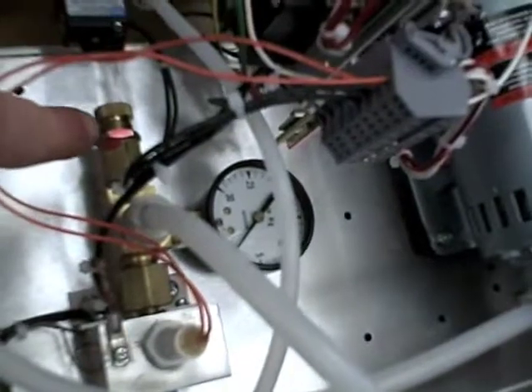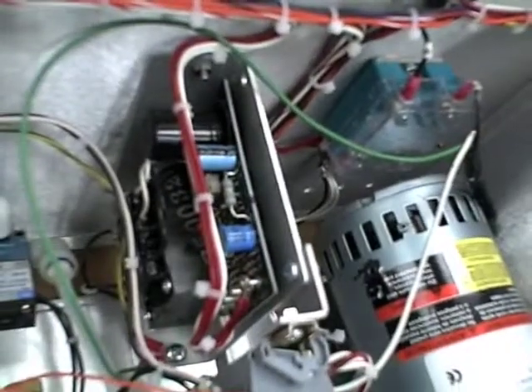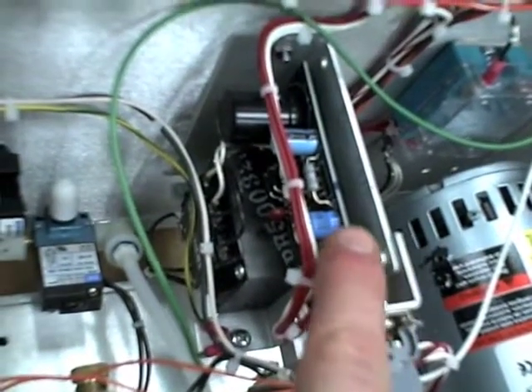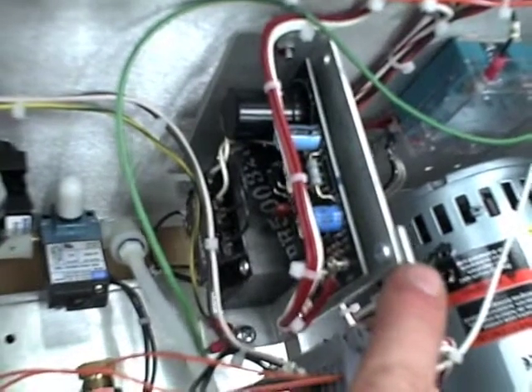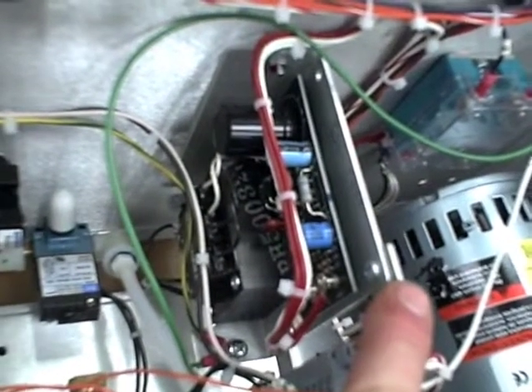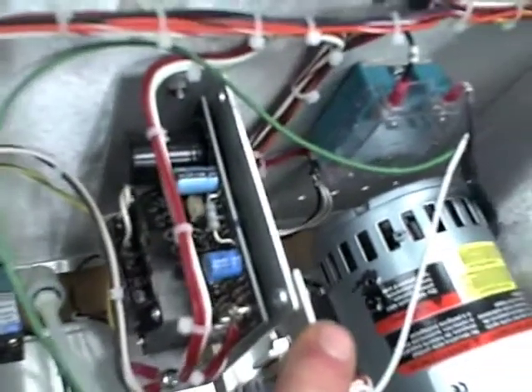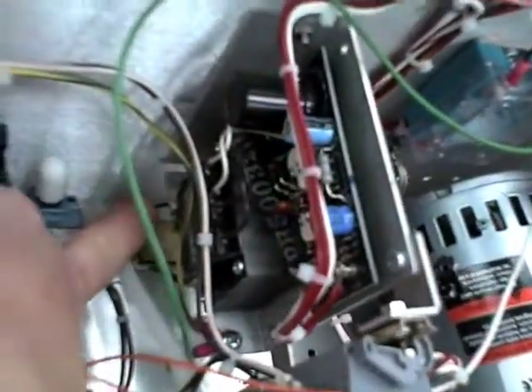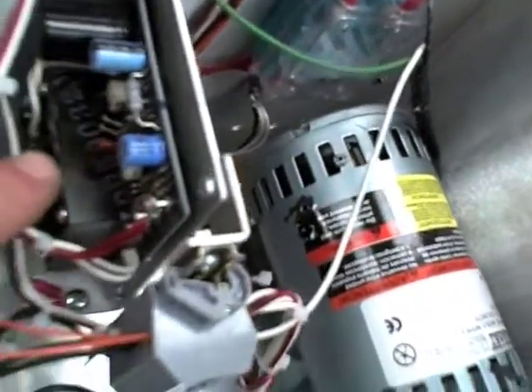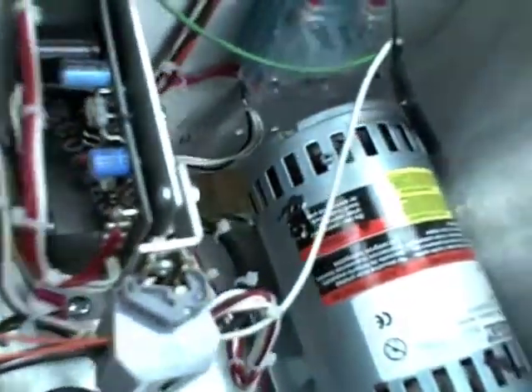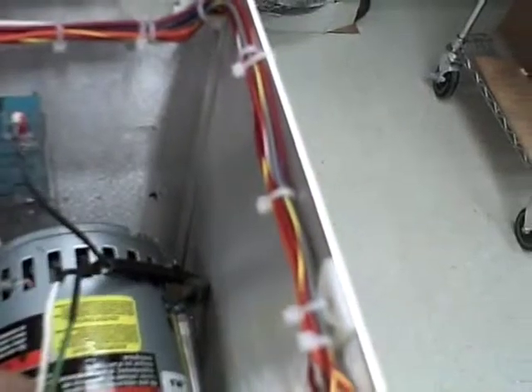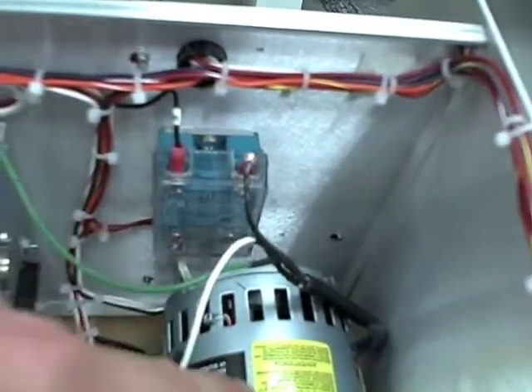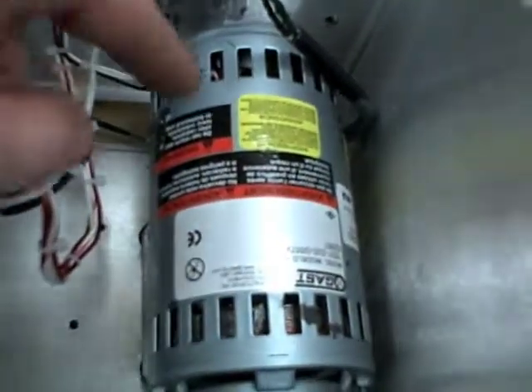We'll see a vacuum relief adjusting knob on the back here, and then a vacuum gauge which shows inches of mercury, inches of Hg. This is going to be a 24 volt transformer, so it's taking 110 volt line voltage and stepping it down to 24 volts DC, and that's what we use for the control of the PLC and for the solenoid valves and the beepers and the lights. So 110 comes in the bottom, and 24 volt comes out where the solid red and white wires are right here. Over here we have the solid state relay, which is going to turn on the vacuum pump, turn it off and on, and then this is the vacuum pump here.